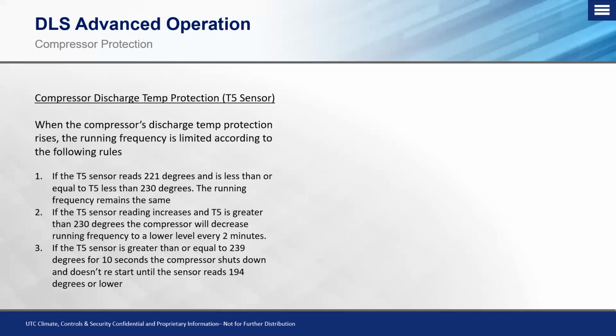Okay, so the whole goal of the sensor is to try to protect the oil from overheating, breaking down, and carbonizing. And this is the main purpose of the sensor. The system has intelligent technology built in to try to throw countermeasures to prevent this temperature from reaching that point. However, even if it goes through its countermeasures and it can't bring down that discharge temperature sensor, it's going to kick off on a T5 code or a compressor discharge temperature code on there. And again, that system will not try to restart until that sensor reads 194 degrees or less.